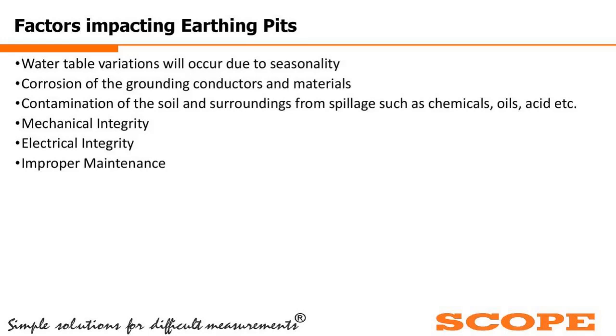Now coming to the factors impacting earth pits. If the water table under the ground varies, the moisture content of the soil also varies. If the water level comes too close to the surface, the moisture content of the soil increases, but if the water level goes down, the moisture content also goes down. The water table varies with seasonality: in the dry season the water level goes down, and in the rainy season the water table remains very near to the ground. So in that fashion it is changing.